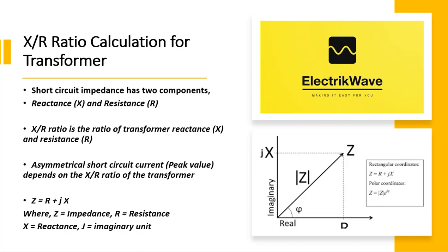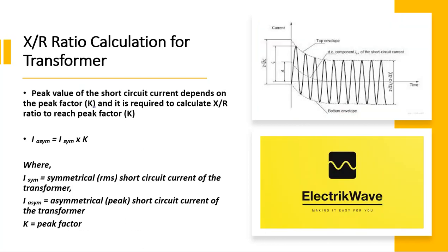Where Z equals impedance, R equals resistance, X equals reactance, and j equals imaginary unit. Peak value of the short circuit current depends on the peak factor K, and it is required to calculate X by R ratio to reach peak factor K. I_asymmetrical equals I_symmetrical multiplied by K.